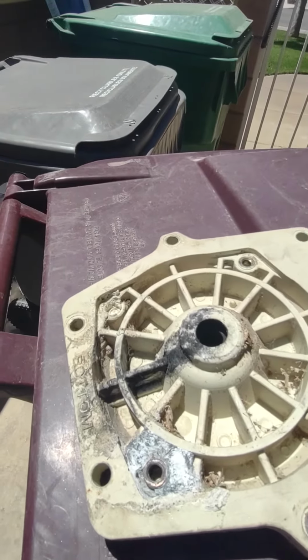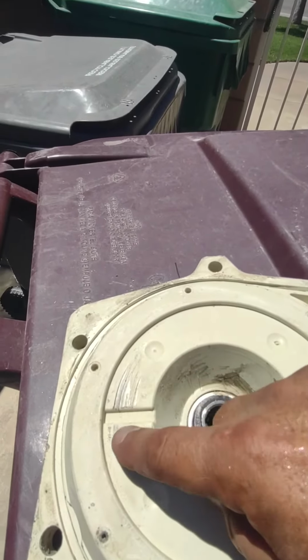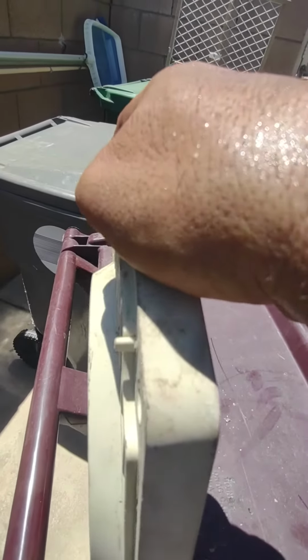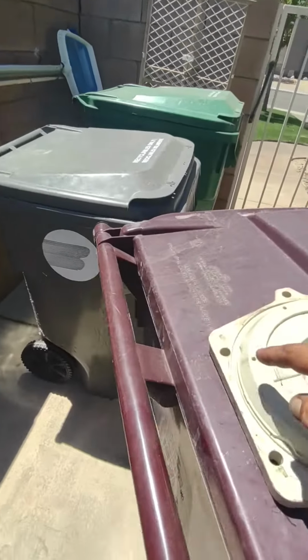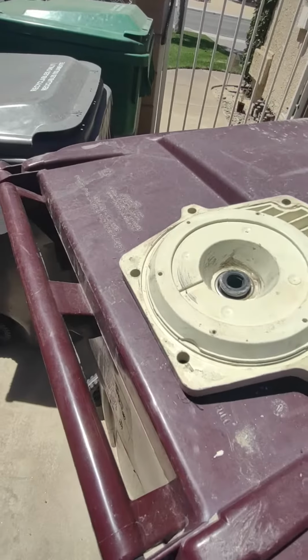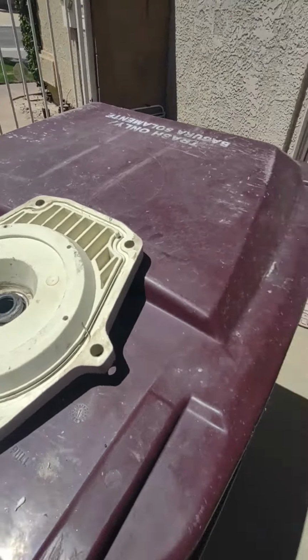Well, what ends up happening is the impeller starts to rub on the inside, because this is staying straight up and down, but the motor's doing this, and since the impeller is attached to it, it also does that, and it starts to rub on it.